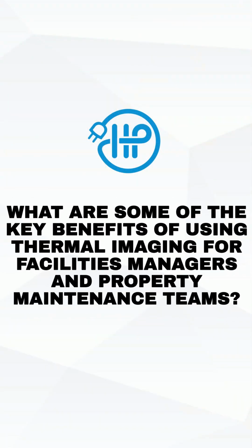What are some of the key benefits of using thermal imaging for facilities managers and property maintenance teams? The key benefits of thermal imaging is to get ahead of a problem like an overloaded circuit before it becomes a bigger problem like some failed devices or a cooked panel, or in the worst case scenario that we have seen, an overloaded phase where the complete destruction of switchgear happened and they were 2 months out to get new switchgear. So getting ahead of those massive problems with some small preventative maintenance billing, that's a huge factor.